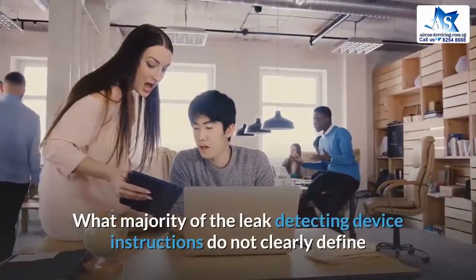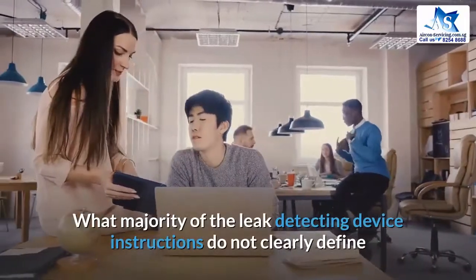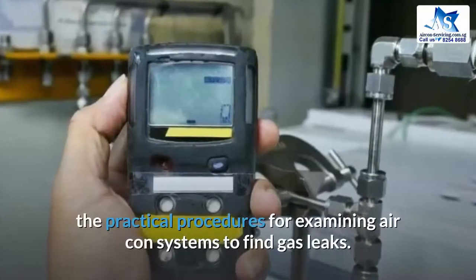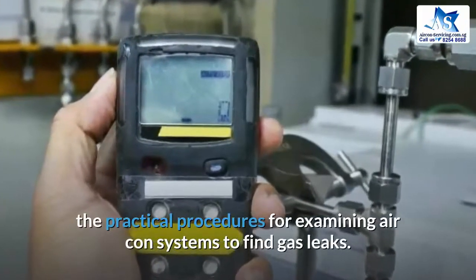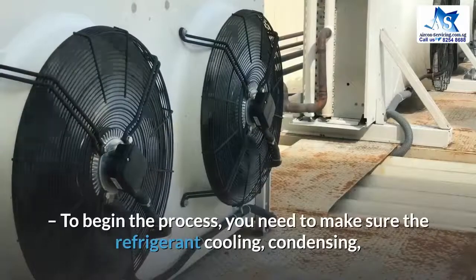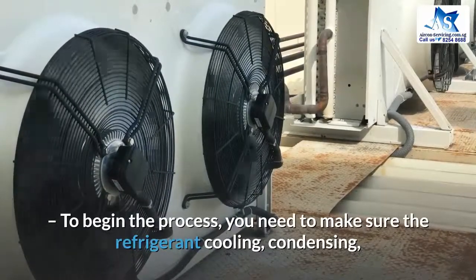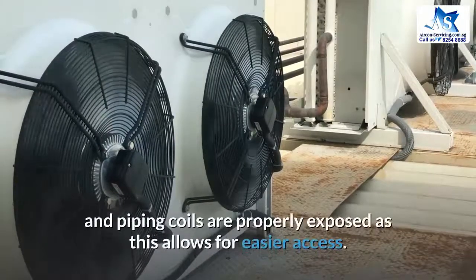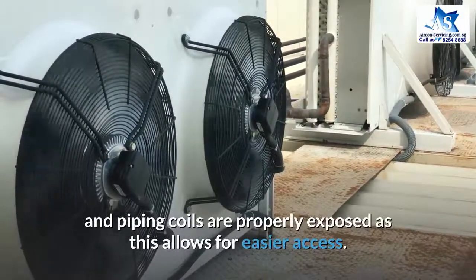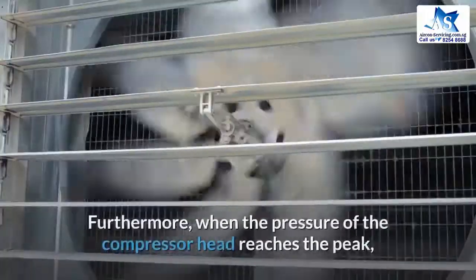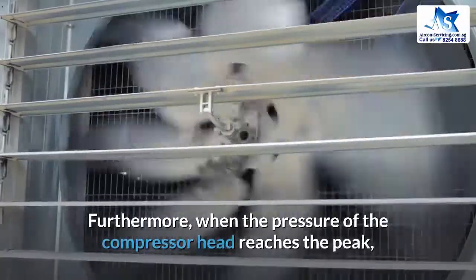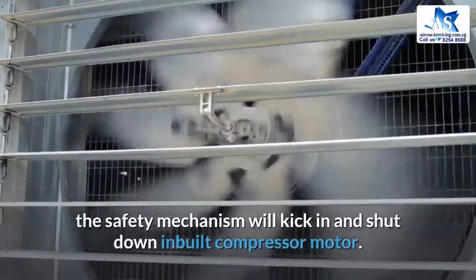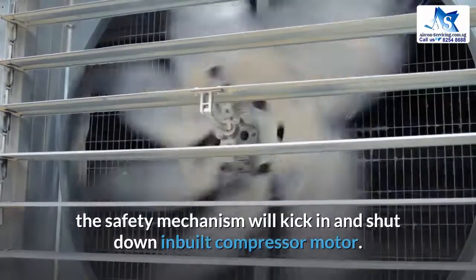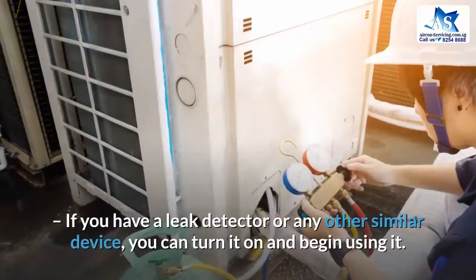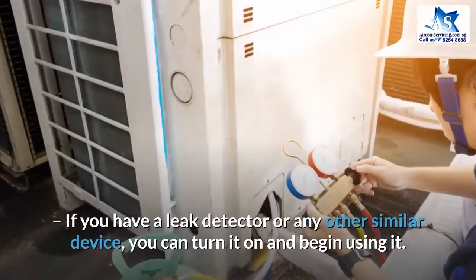The majority of leak detecting device instructions do not clearly define the practical procedures for examining aircon systems to find gas leaks. To begin the process, you need to make sure the refrigerant cooling, condensing, and piping coils are properly exposed, as this allows for easier access. Furthermore, when the pressure of the compressor head reaches the peak, the safety mechanism will kick in and shut down the inbuilt compressor motor.